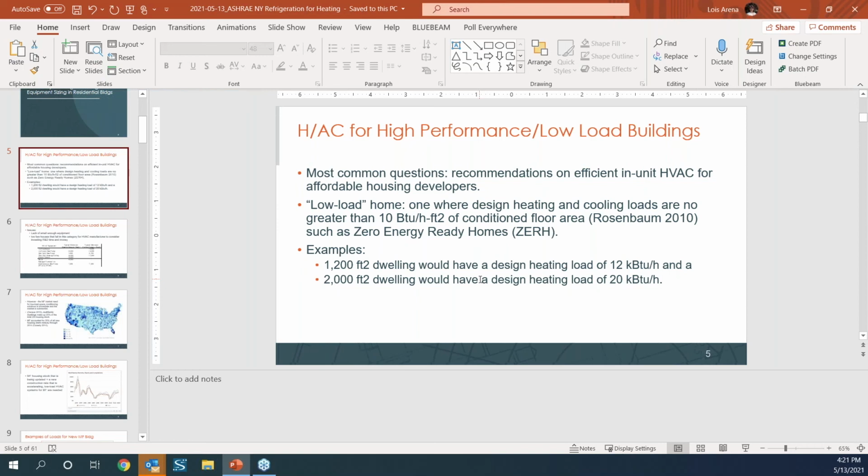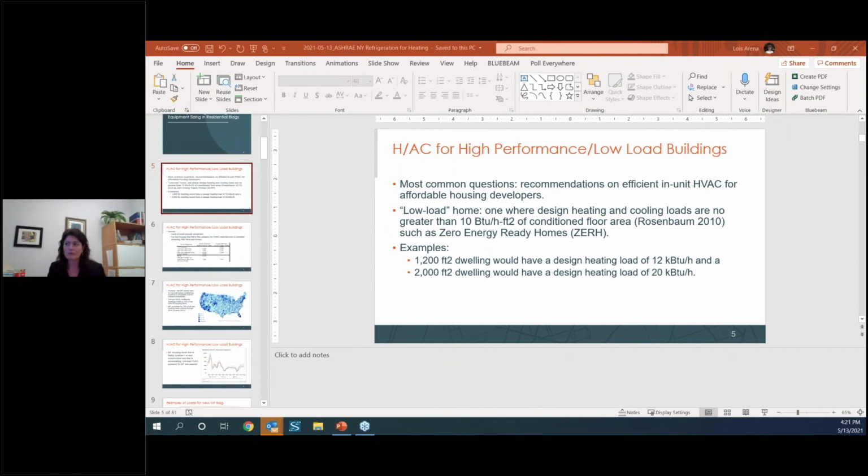Okay, great. Next, on the example projects you gave, was any consideration given to heat pump domestic hot water systems for these projects? If yes, what drove the choice to use gas? Yeah, we're trying to do that, and New York's really pushing us to electrify these buildings throughout. The cold climate heat pumps for domestic just don't put out hot enough hot water for reliable cold climate, really low temp production. You really need to beef up your storage and then have some sort of backup.